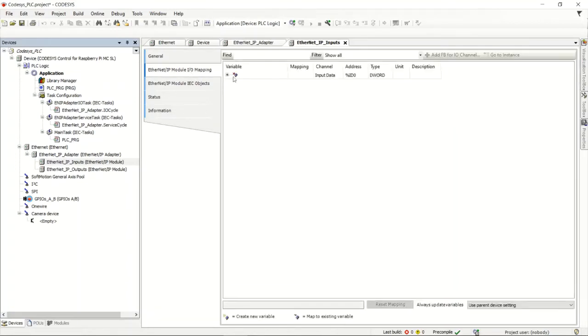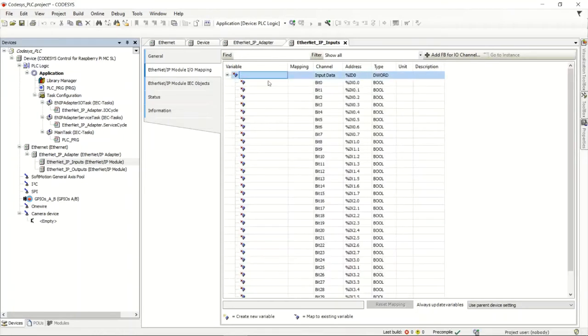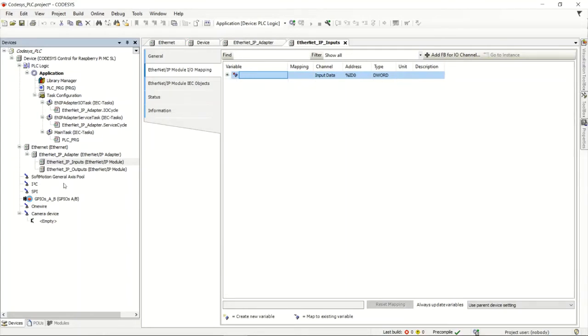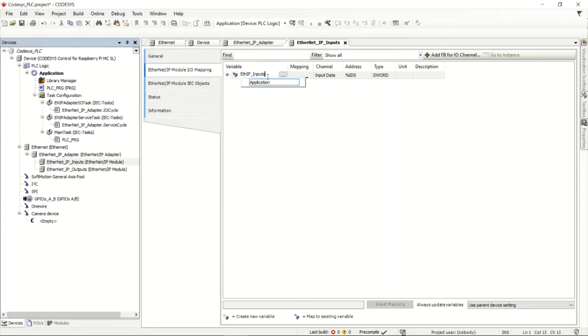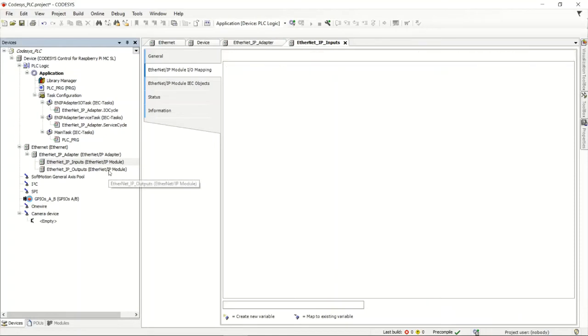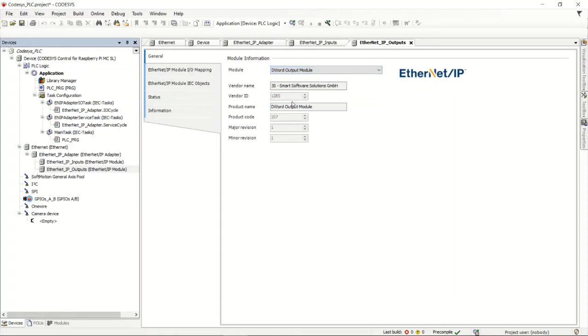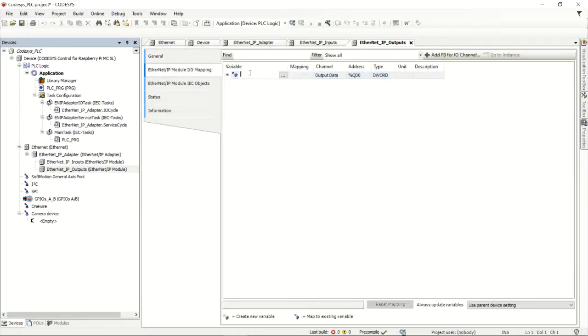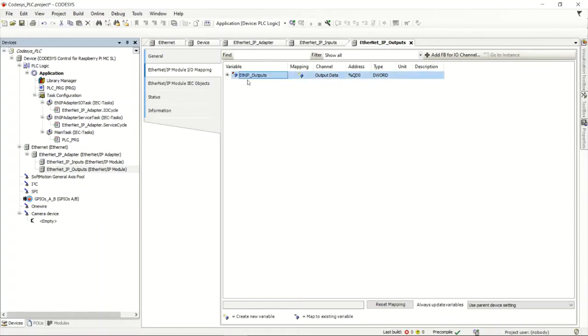Now we go into the actual mapping of the I/O — this is the first time in our YouTube series that we've seen mapping. Mapping of I/O is done through words like this that you want to transfer back and forth, but real I/O can be mapped this way as well. When you open it up it breaks out into individual bits. You're basically connecting a tag to the real I/O. I'll create a tag called 'ENIP_Inputs'. For the output I'll also select D-word output and map it to 'ENIP_Outputs'.